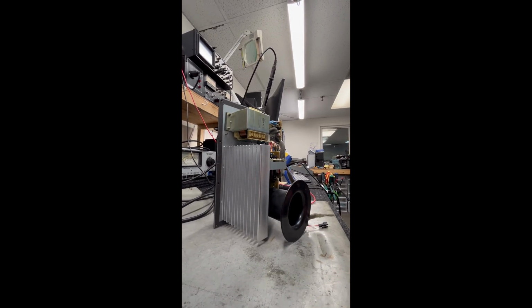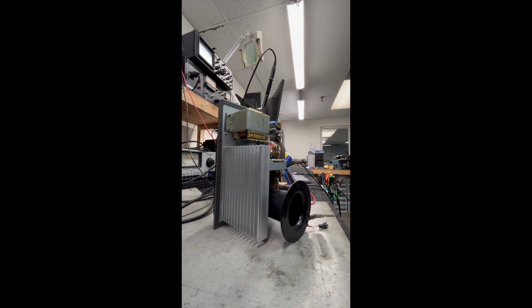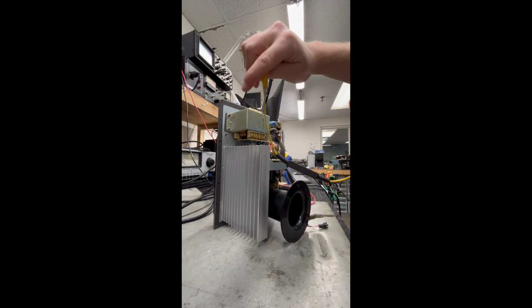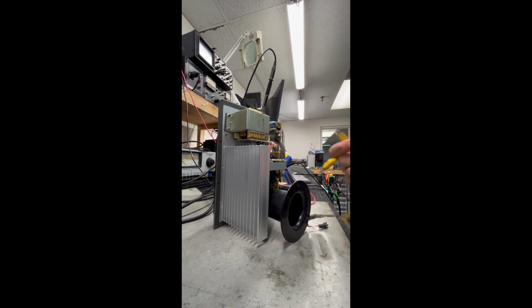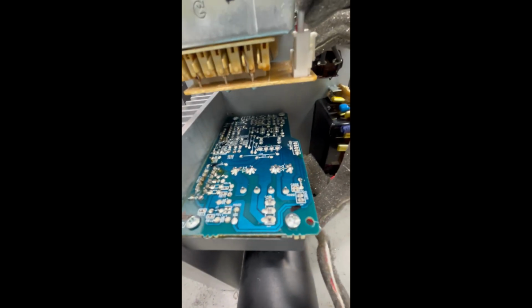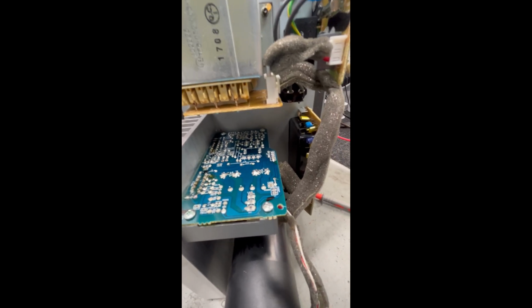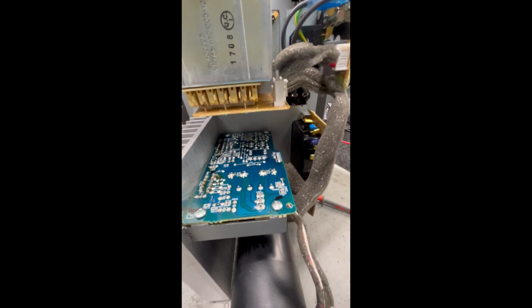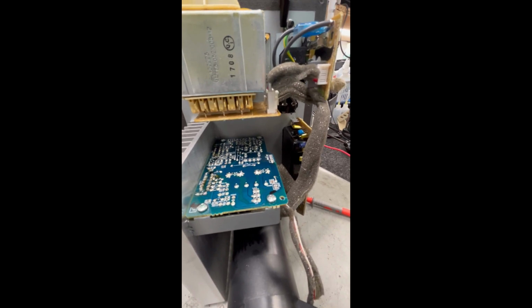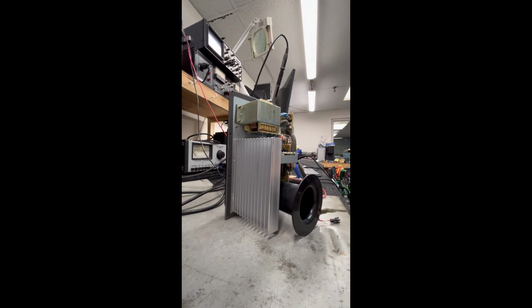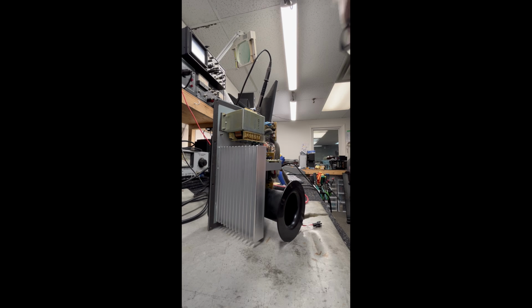If you're working on something like this and you're worried about getting shocked, even when it's off, good practice is to take a discharging tool. Basically just a large wattage resistor at a lower value, which is built into this here, and put it across these nodes here. So put it across the capacitors themselves, or put one end of the lead to ground and then the positive end to the positive side of the cap in order to discharge it. That way you know you don't have any excess voltage lurking about in your circuit, and you don't blow anything while tapping around.